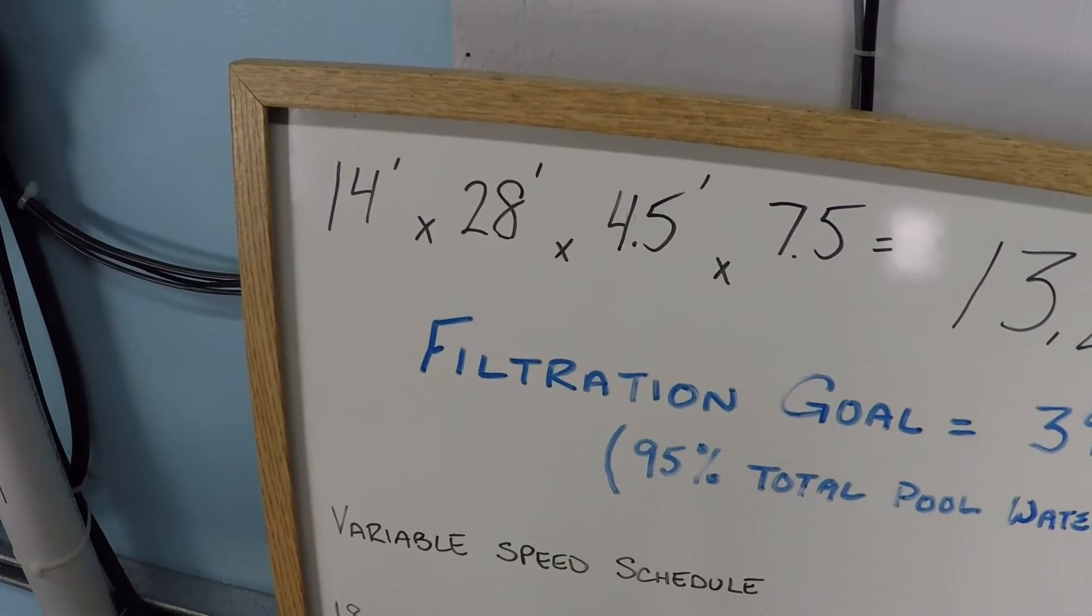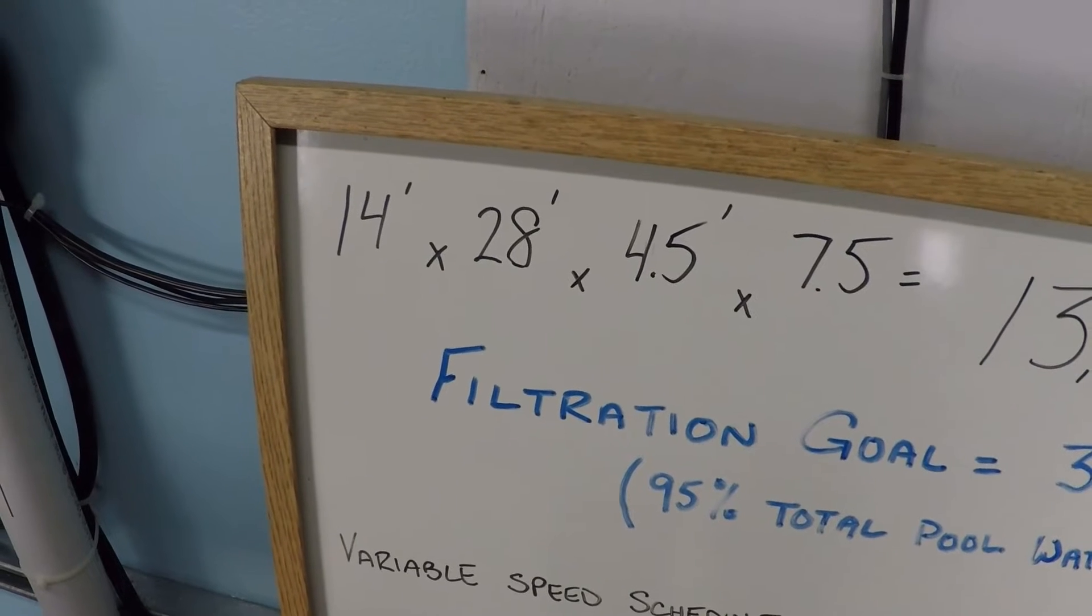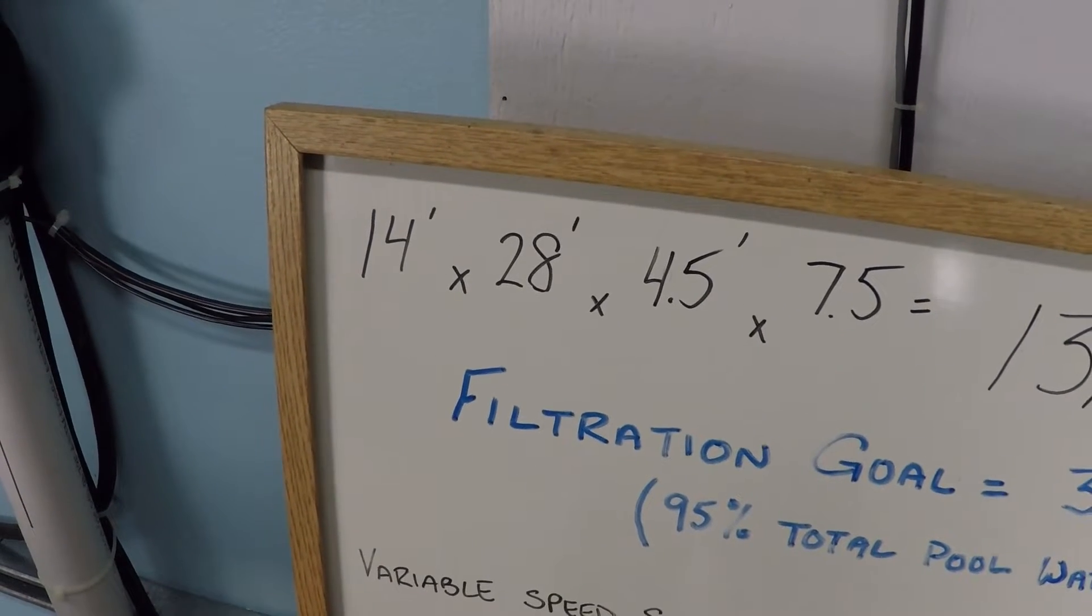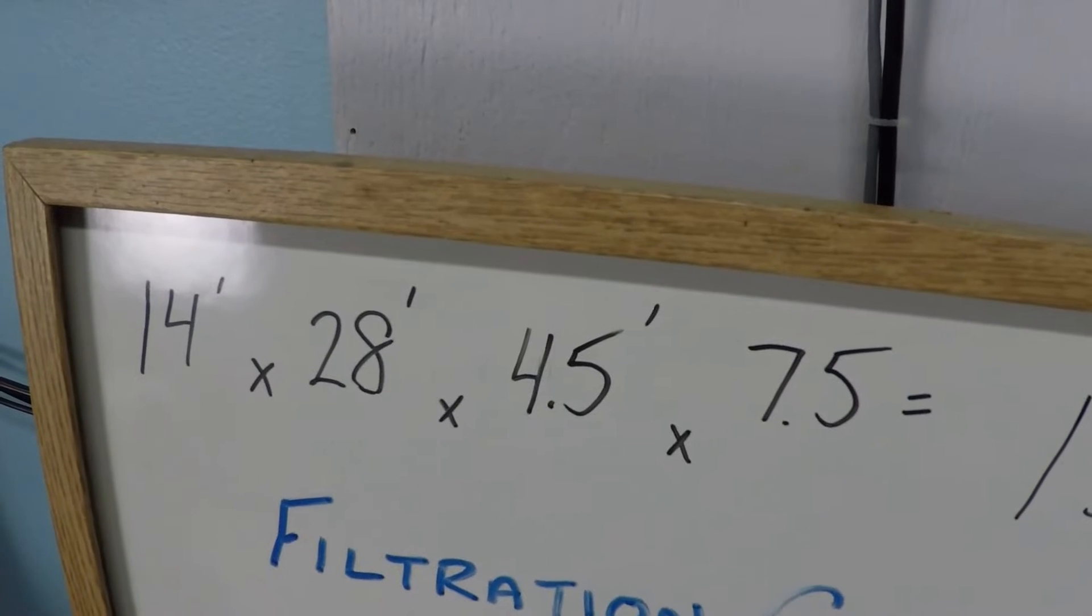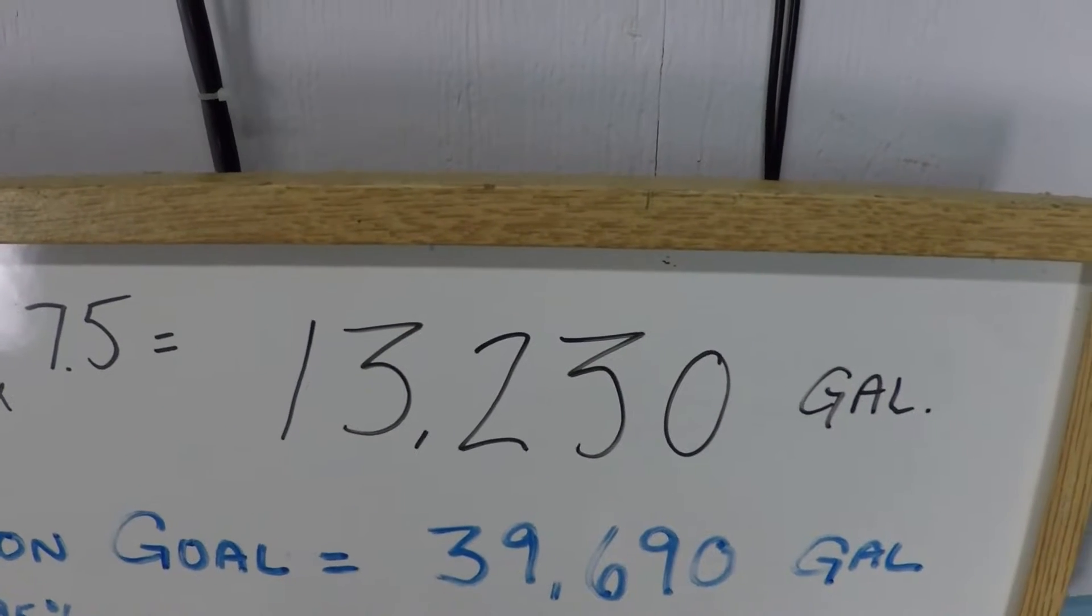In this video, we're going to be designing a filtration schedule for a 14 by 28 foot swimming pool with a variable speed swimming pool pump. The average depth of this pool is about 4.5 feet, so it's 13,000 gallons, or just a little bit over.